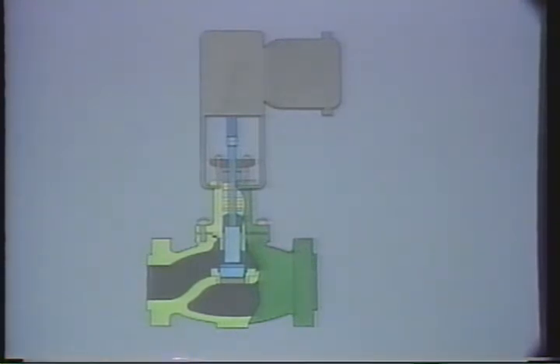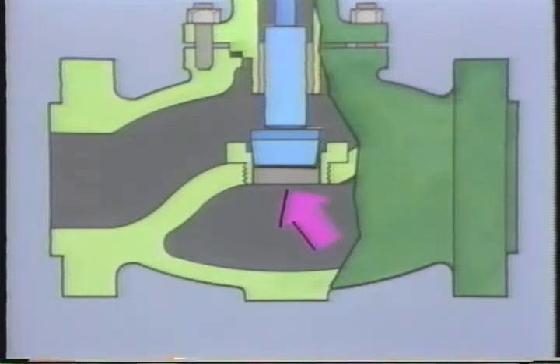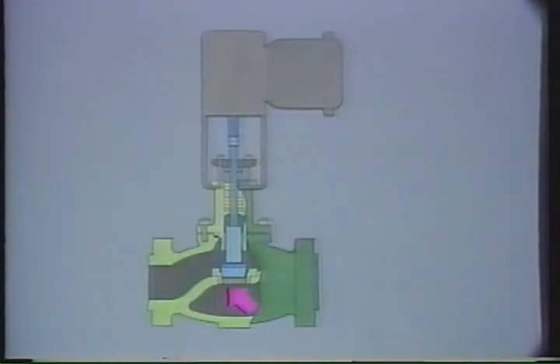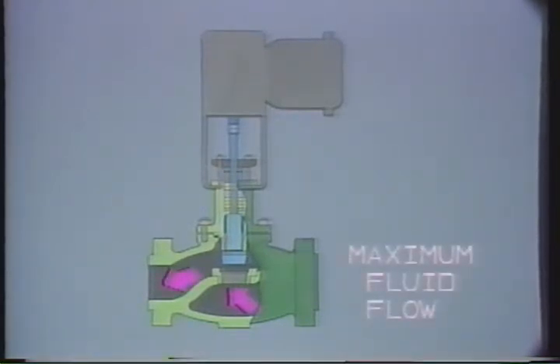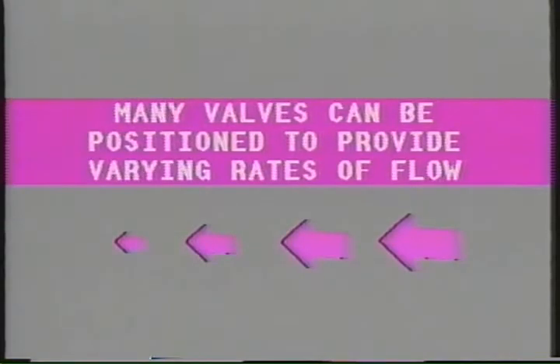When the plug and seat meet, the valve is closed. In this valve, when it is in the closed position, no usable flow passes through the device. When the plug is as far away from the seat as it can go, the valve is at the fully opened position. In the fully opened position, the maximum amount of processed fluid flows through. Many valves can be positioned at several points in between closed and fully open to provide varying rates of flow through the valve.